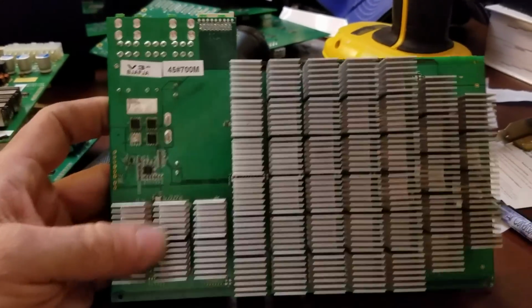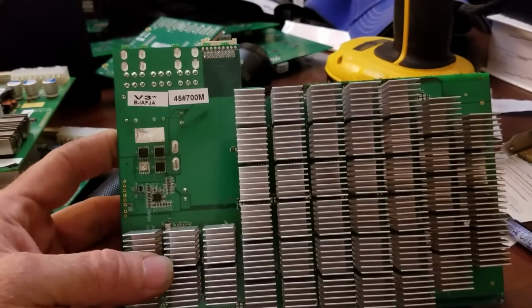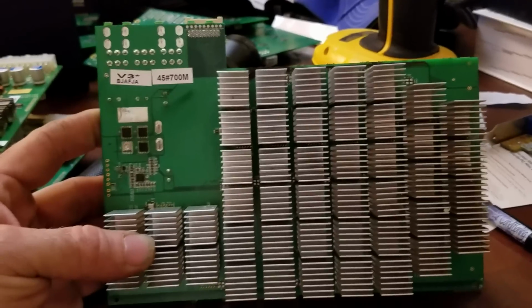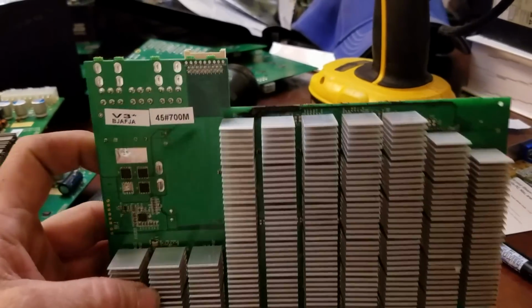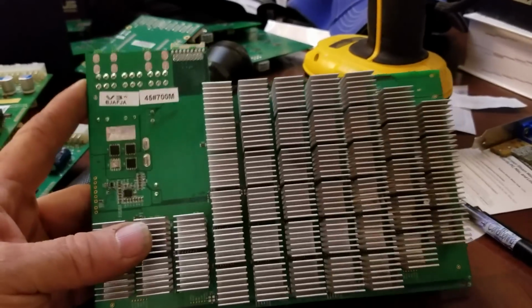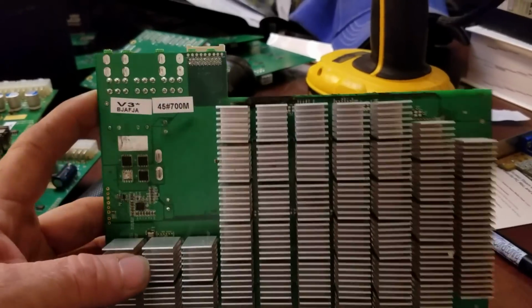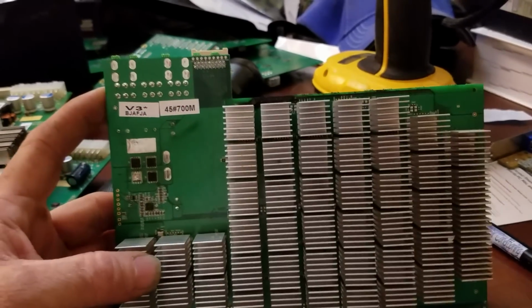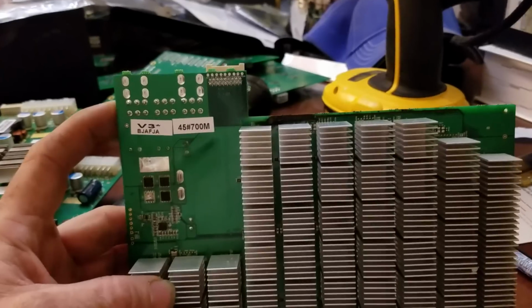When the airflow is reduced, either by, let's say, a dirty filter causing the reduction of the amount of air passing through it, this puts a strain on most fans. I only use variable speed fans because they're able to overcome any type of static pressure. And if you're going to run a large mine, you're going to have to use high RPM, variable speed, modulated fans, where the speed is going to be based on the RPMs.